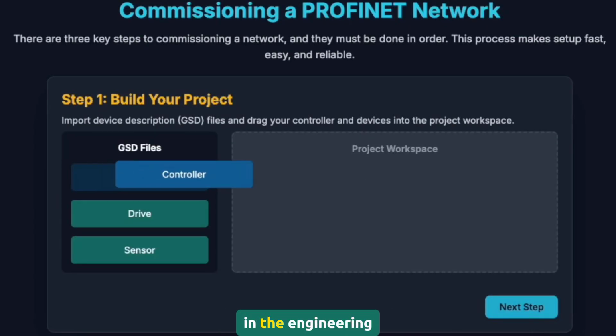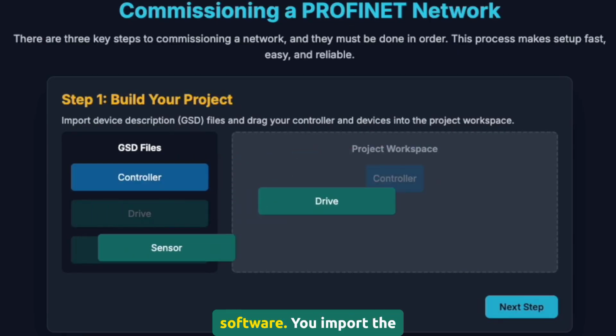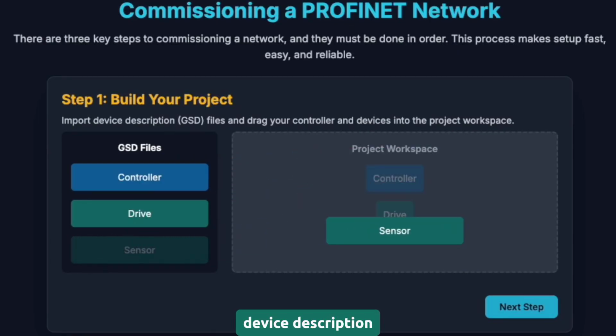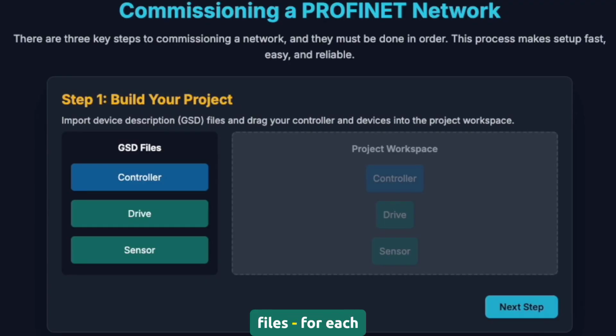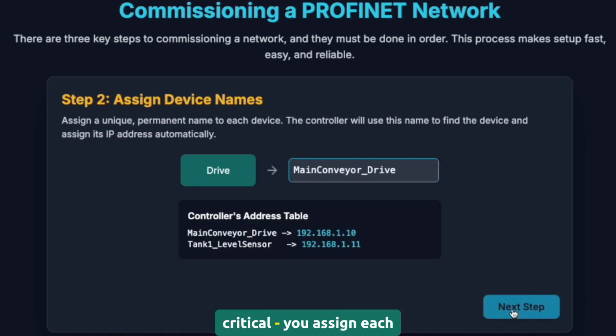Build your project in the engineering software. You import the device description files, GSD files, for each device, then drag and drop your controller and all your devices into the project. Step 2 is critical. You assign each device a unique name. Not just an IP address, but an actual name like main conveyor drive or tank 1 level sensor. This name gets burned into the device and becomes its permanent identity.